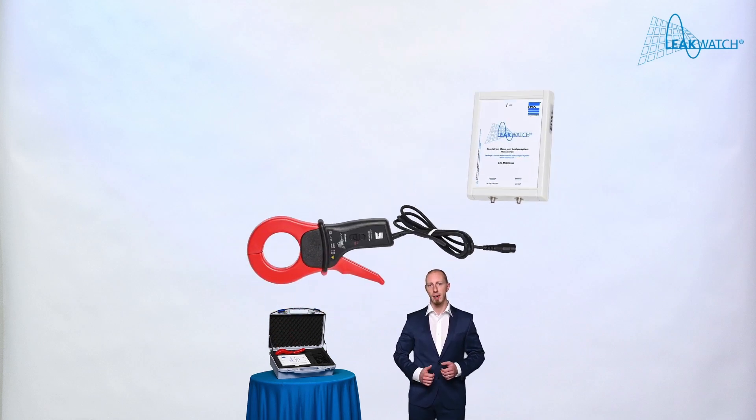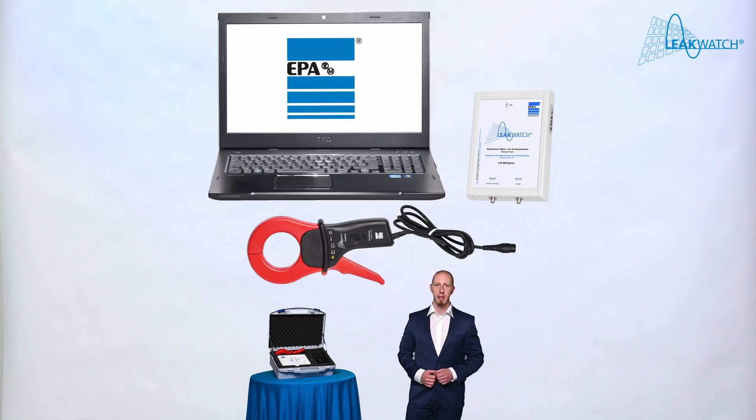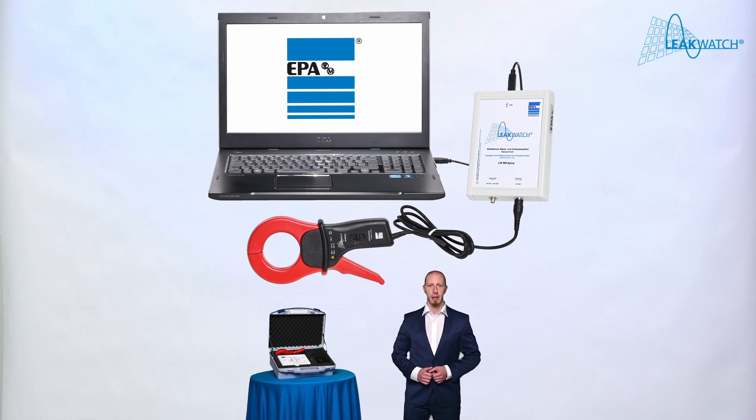The Leakwatch measuring and analyzer system consists of the measuring unit and the measuring transformer, in this case a measuring clamp. For evaluation and displaying the measured values, a PC or laptop with a Windows operating system is additionally required. The measuring unit is connected to the laptop via a USB cable. The measuring clamp is placed around the outer conductors as described before.